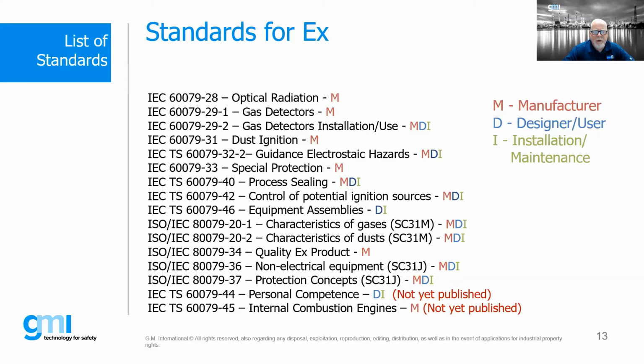Now there's also some other standards you may or may not be familiar with, the 80079 set of standards. There's 20-1, 20-2. These give you the details as to the characteristics of gases and dust. So if we want to find out exactly what the ignition temperature is of various gases, or what gas groups they would fall into, these documents will give you a lot of that information. If I'm manufacturing EX equipment, the dash 34 standard has been updated, and it's now putting much more onerous requirements upon manufacturers to make sure their quality process on manufacturing EX equipment is very much up to date.